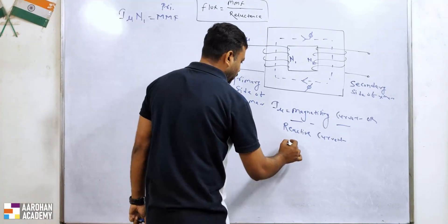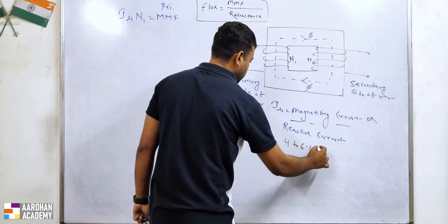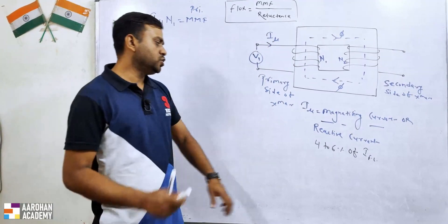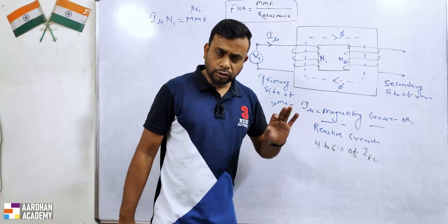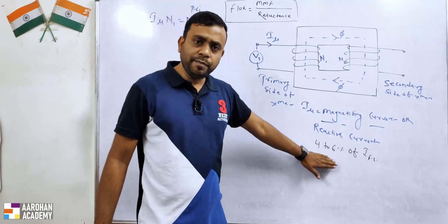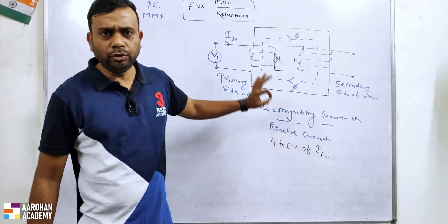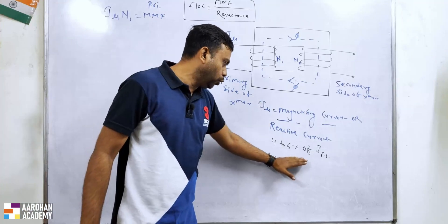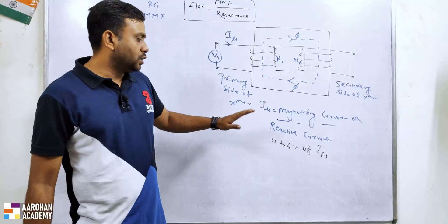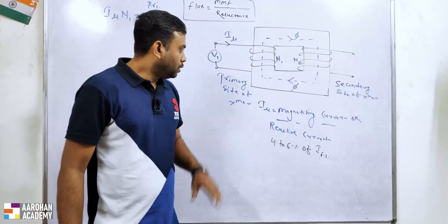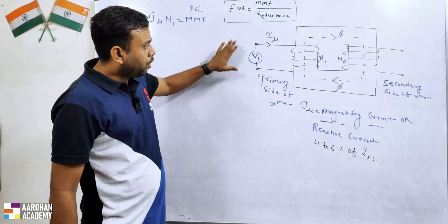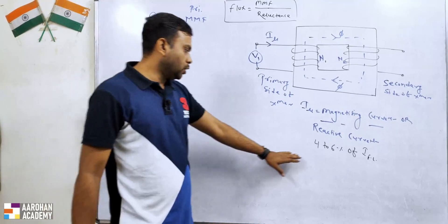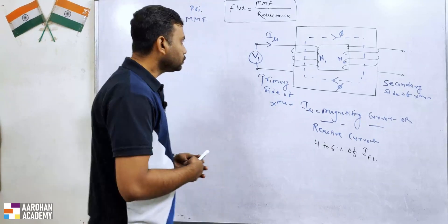This magnetizing current will be in the range of 4 to 6 percent of the full load current. Now the question arises: if we increase Imu beyond this range, what will happen to the transformer, and why do we take Imu only in the range of 4 to 6 percent? I'll give the answer in the coming videos. Right now our topic is to focus on how the induced EMF lags behind the flux.